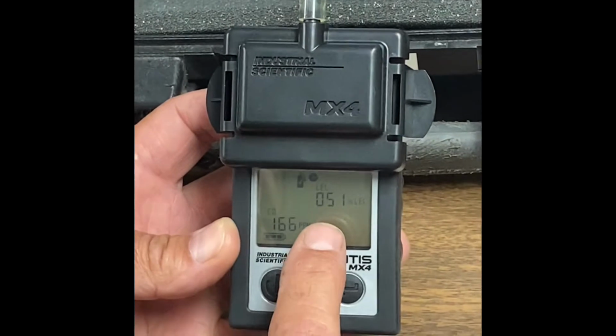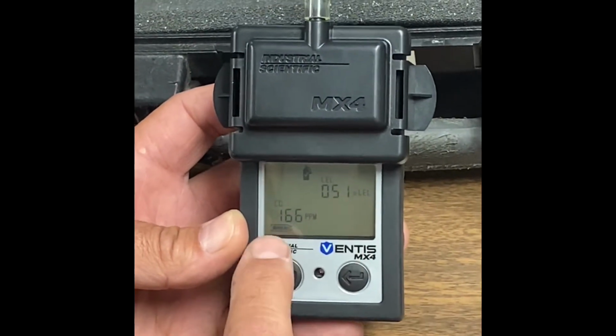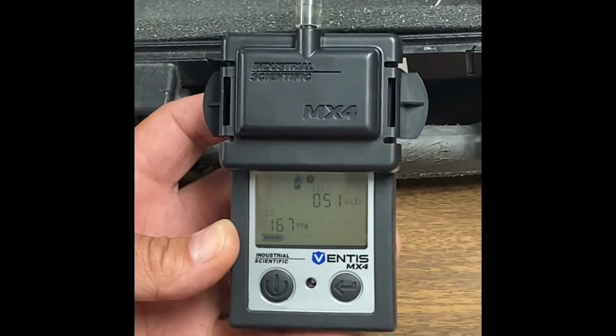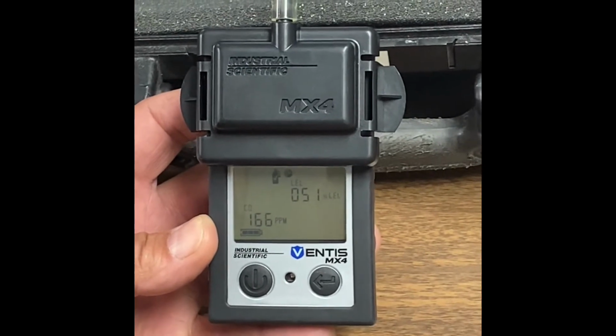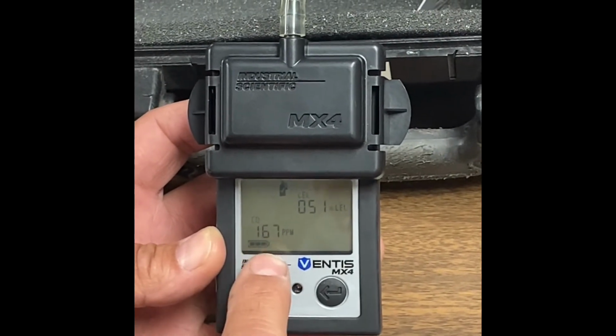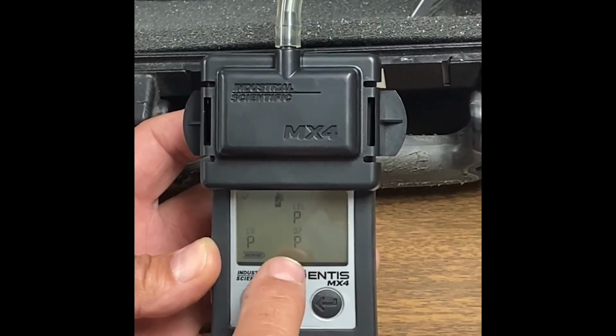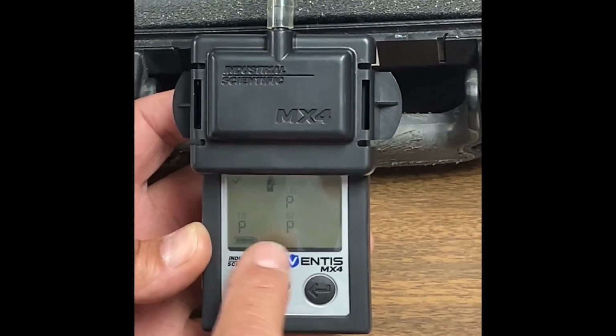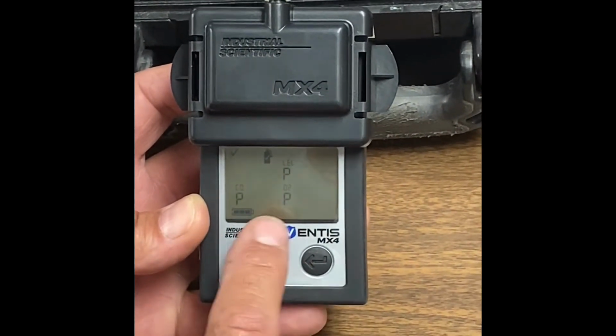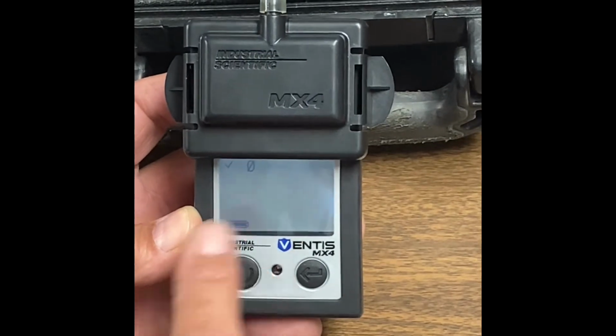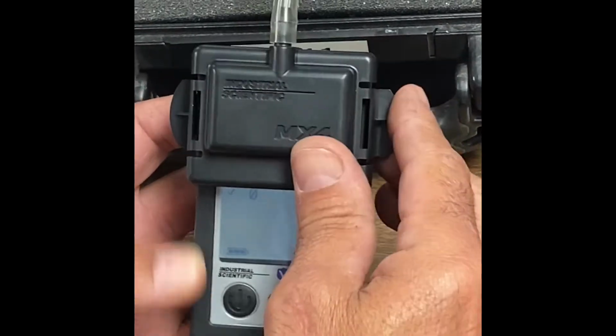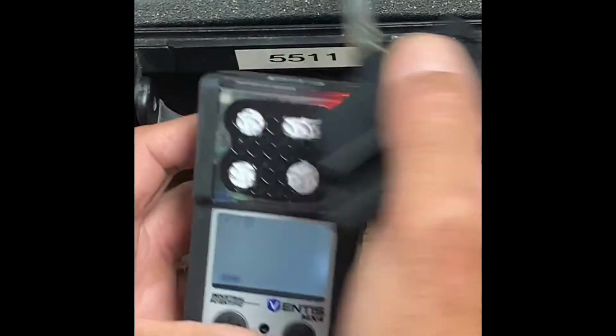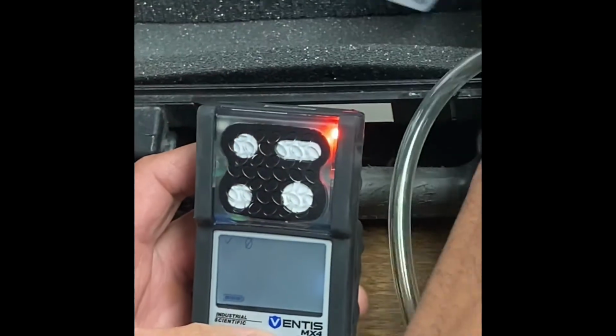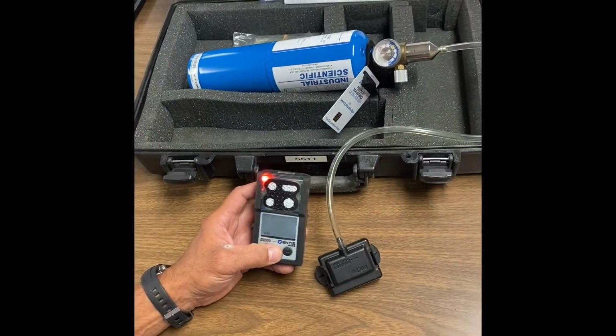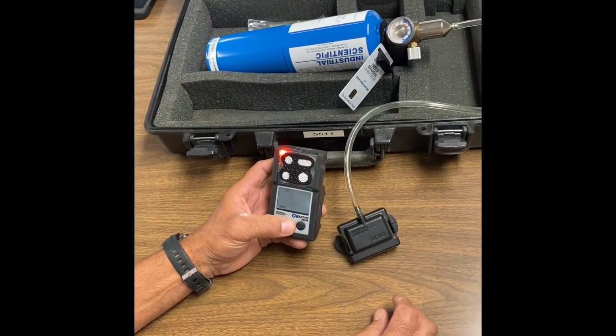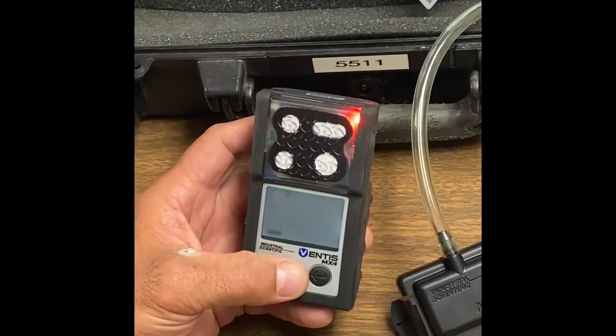You're going to see the numbers start leveling off, 51,166. So you write 51,166, and you want to make sure you catch the final number. So you got 3 P's, 51,166, and make sure you note the other number. And at that point, you got 3 P's. You can disconnect the calibration cup, turn off your gas, and your unit has now been calibrated.